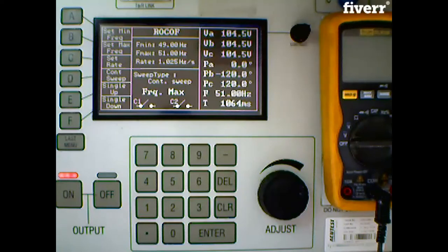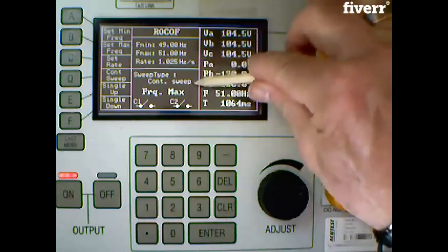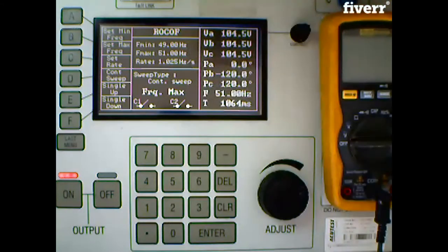But you've got to be mindful that there might just be a pedantic DNO that wouldn't want that timing. If he didn't want that timing, you'd have to put a different relay in, because there's literally nothing else that you can do. There's no other settings you can change, because our settings here are fixed. Our settings on the relay are fixed other than the filter. And we've tried the filter on every setting from 1 to 37. So we know it's not going to get any quicker with this relay than 1064.